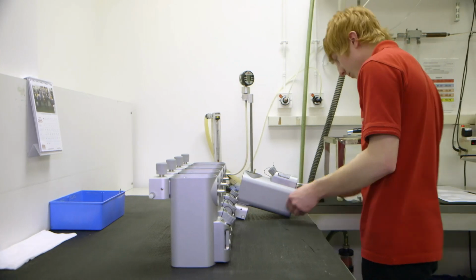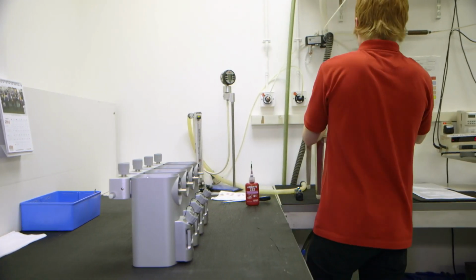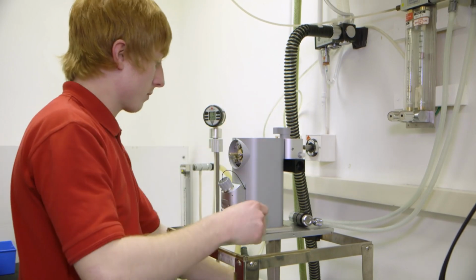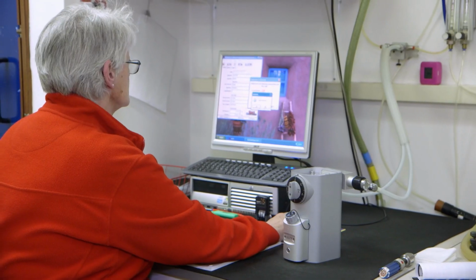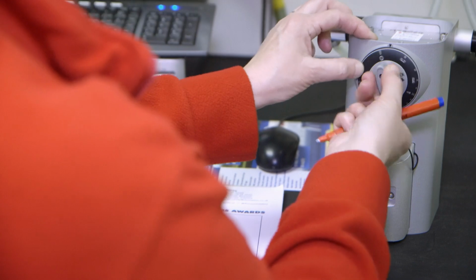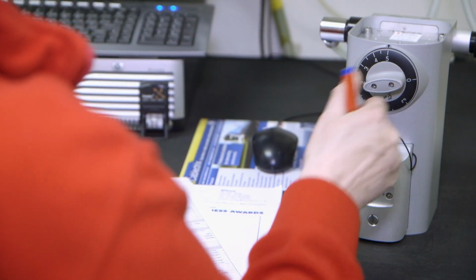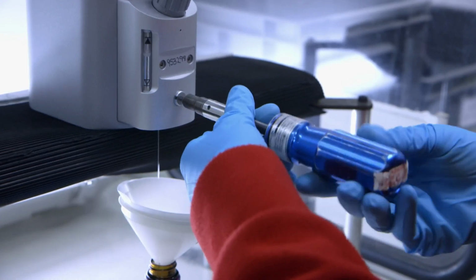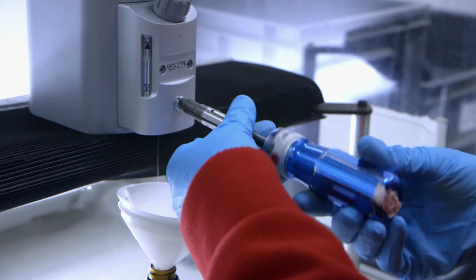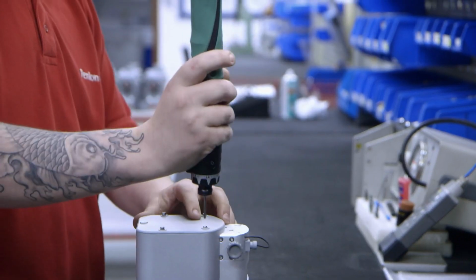Pre-calibration, we fill the vaporizer up with agent because it needs to be calibrated with agent in the vaporizer. We then sit the vaporizers for 2 hours to climatise. They then go into the test room where they're calibrated using laser refractometers. These components go through rigorous quality control checks, with gases being passed through the devices and the results being scrutinised. After testing, the vaporizers are drained and dried, so no residual liquids are left inside. Then the filler block is assembled.